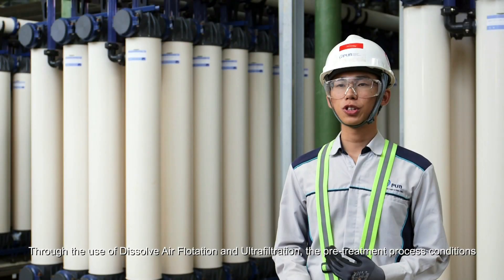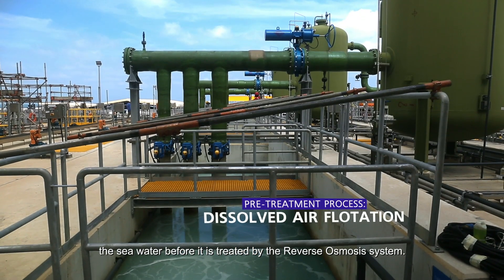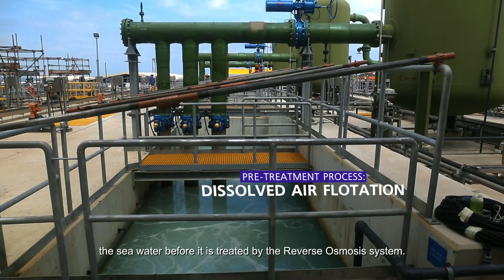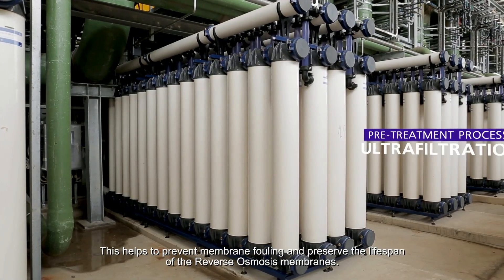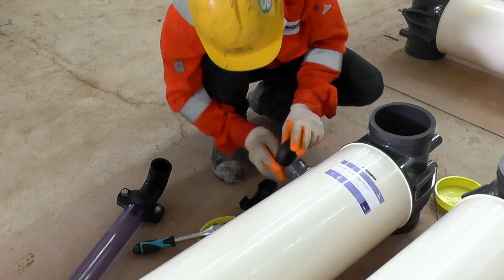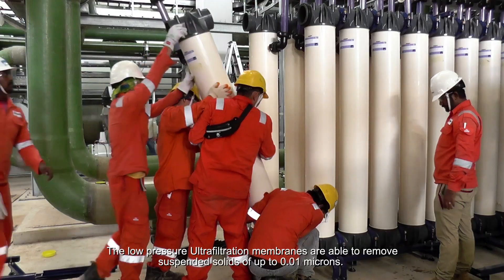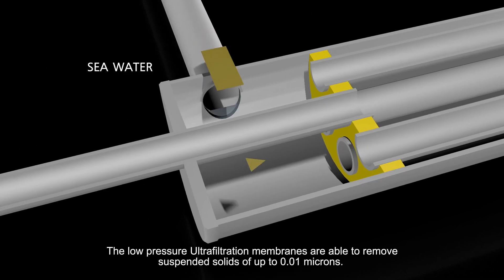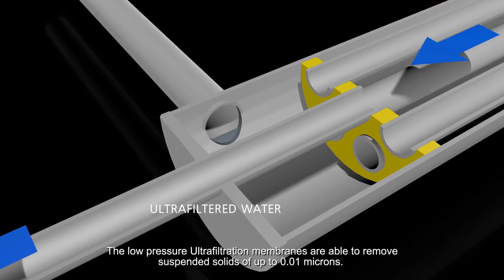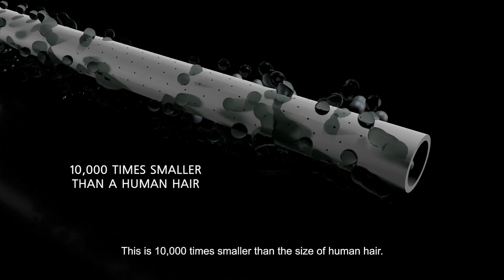Through the use of dissolved air flotation and ultrafiltration, the pretreatment process conditions the seawater before it is treated by the reverse osmosis system. This helps to prevent membrane fouling and preserve the lifespan of reverse osmosis membranes. The low-pressure ultrafiltration membranes are able to remove suspended solids of up to 0.01 microns — 10,000 times smaller than the size of human hair.